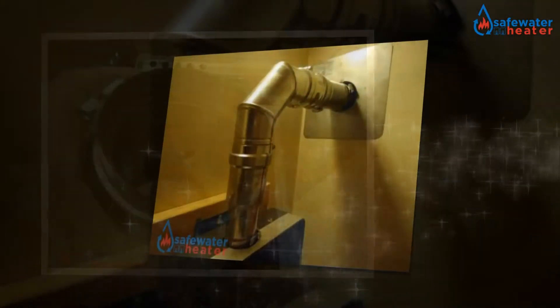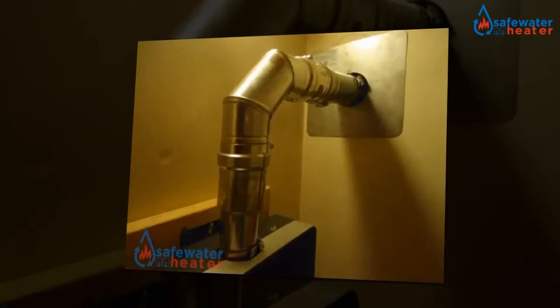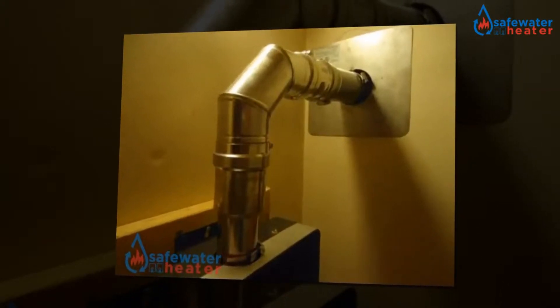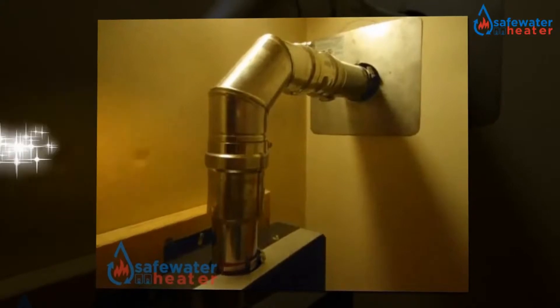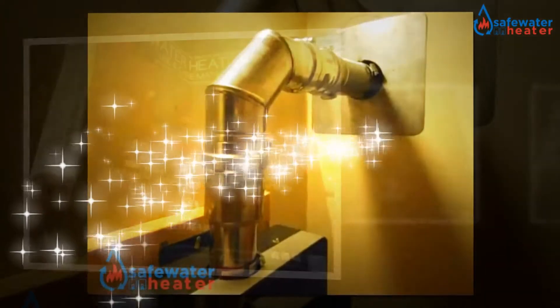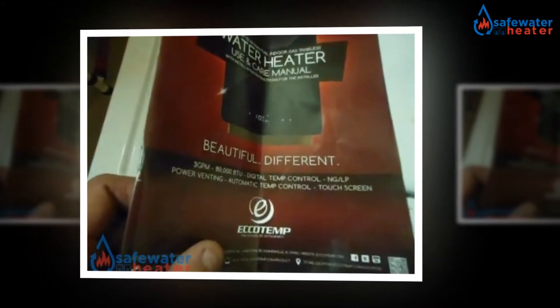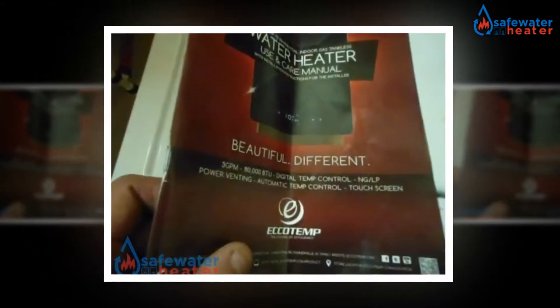The Eccotemp i12-LP is powered with liquid propane. The indoor model is designed for smaller to medium quick hot water production where you want more than one hot water application working at the same time. This model gives about 35 to 40 degree Fahrenheit temperature rise when operated at a flow rate of 4 GPM, and a 77 degree Fahrenheit temperature rise at 1.5 GPM.